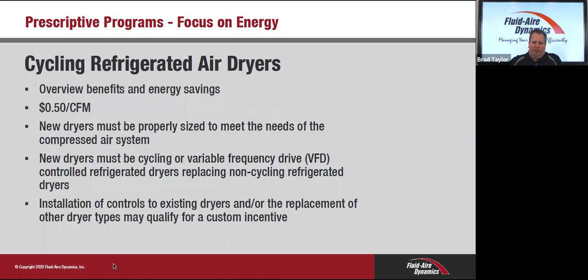So then just jumping into dryers, there are two different types of dryers. I'm sure most on the call are aware: desiccant or refrigerated type. What we're going to talk about is the refrigerated type, specifically the incentives towards cycling type. Up to 200 CFM, the most common type of dryer is a non-cycling or hot gas bypass type dryer. Then above 200 CFM, typically we have either a cycling or variable speed drive type dryer.